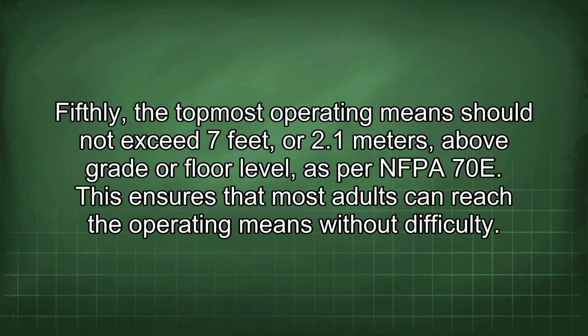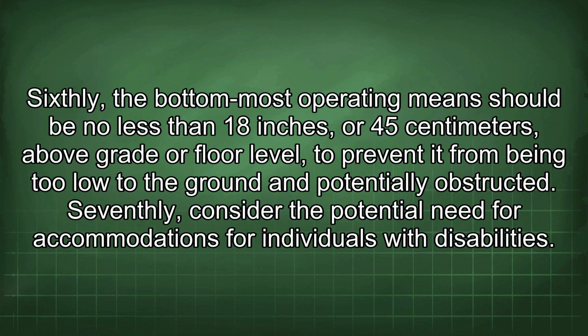Fifthly, the topmost operating means should not exceed 7 feet, or 2.1 meters, above grade or floor level, as per NFPA 70E. This ensures that most adults can reach the operating means without difficulty. Sixthly, the bottommost operating means should be no less than 18 inches, or 45 centimeters, above grade or floor level to prevent it from being too low to the ground and potentially obstructed.